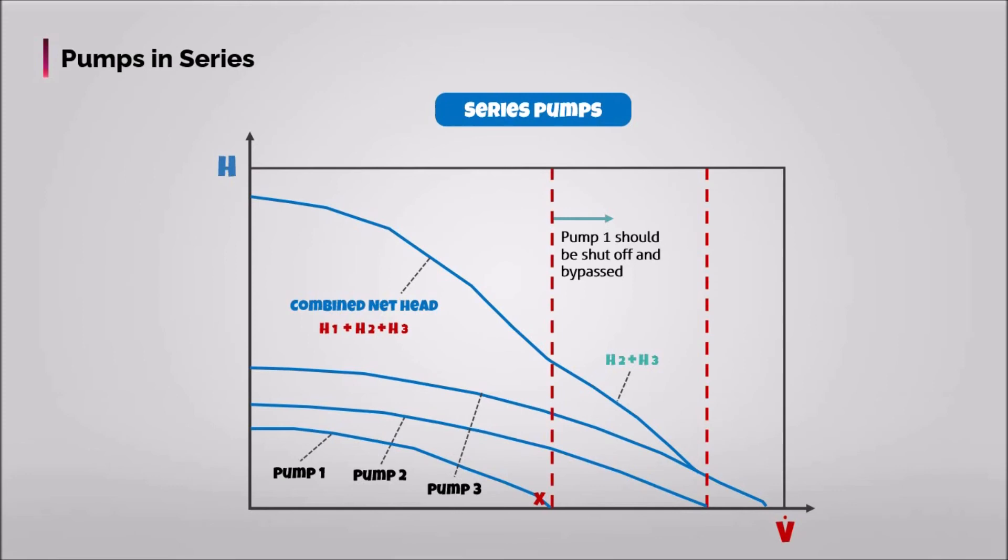Following this, in this area only pump two and three operate until reaching the limited point of pump two's delivery, where it should be shut off and bypassed. Consequently, only pump three will contribute in this area, delivering its head H3.